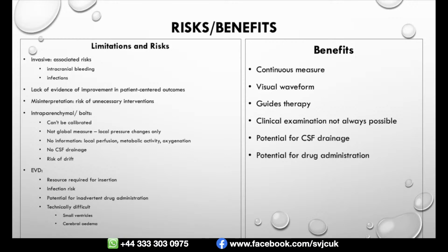So in the context of the bolts, you can't calibrate them. They're not a global measure, so they tell you about local changes only, which may not reflect the entirety of the brain. It doesn't give you any information about local perfusion, local metabolic activity, or oxygenation. You can't drain any CSF, and there is a risk of drift, which increases the longer that the bolt remains in situ.